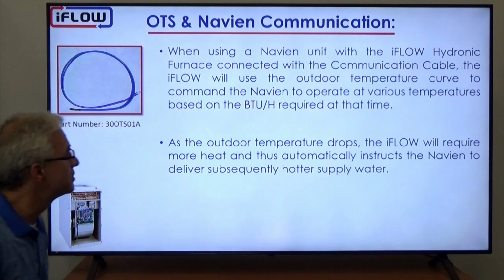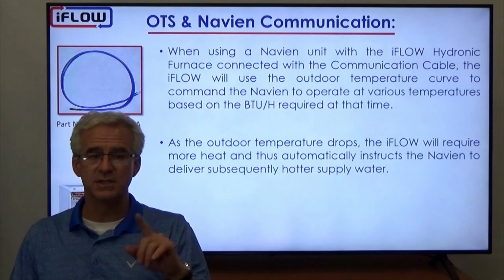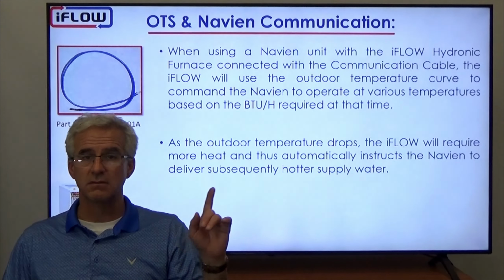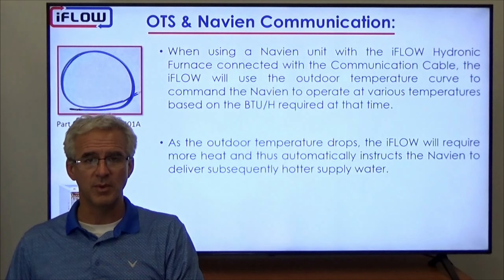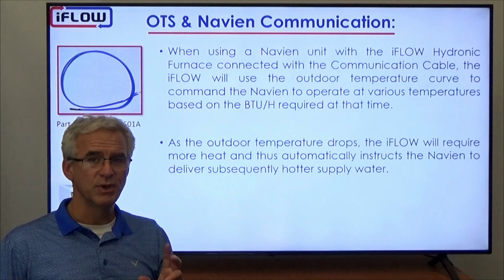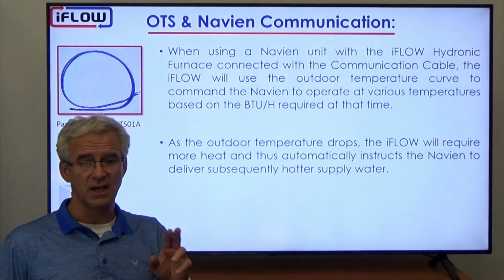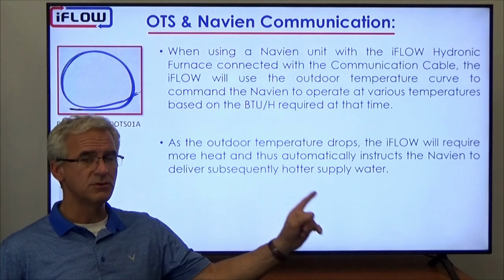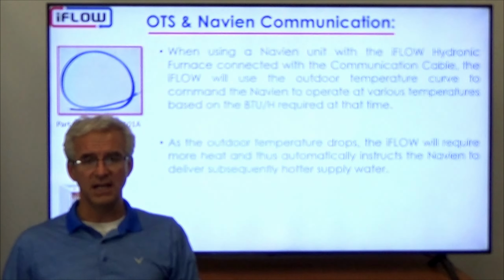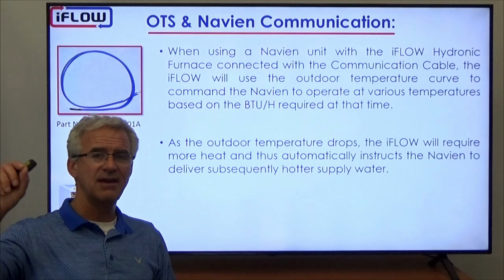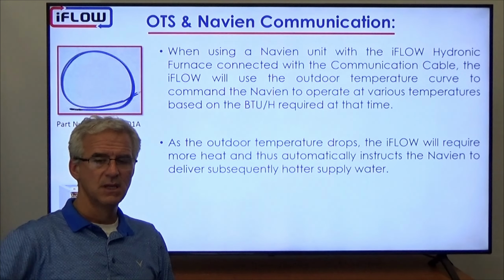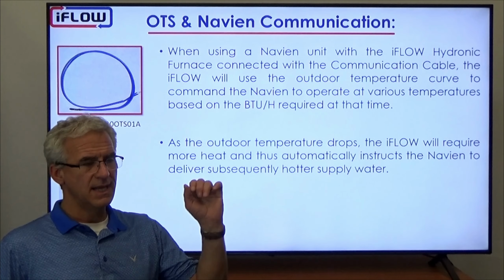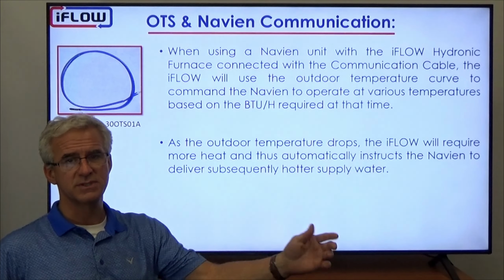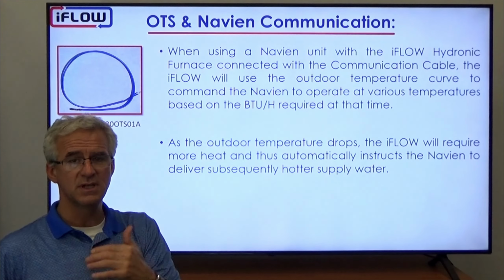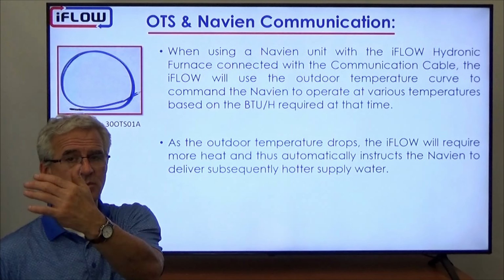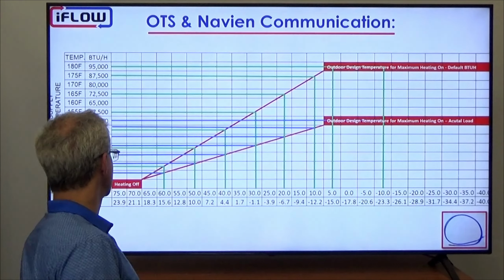Now another special feature, if we are connecting to a Navien tankless water heater or combi boiler, we have the ability to communicate between the iFLOW and the Navien. So the outdoor temperature that's connected to the iFLOW will then tell the Navien what temperature to run at. And you can imagine, as we need more BTUs into the space, so as it gets colder outside, we'll tell the Navien to give us hotter and hotter temperatures. So let's look at what that does.